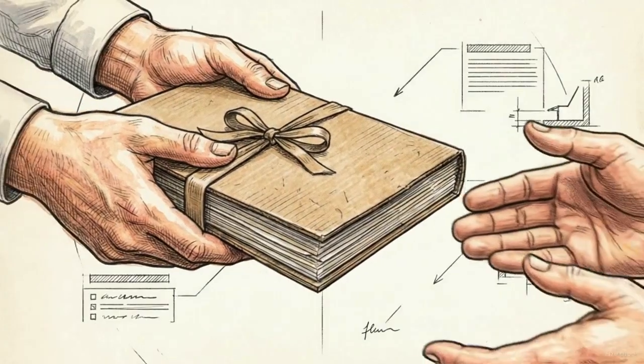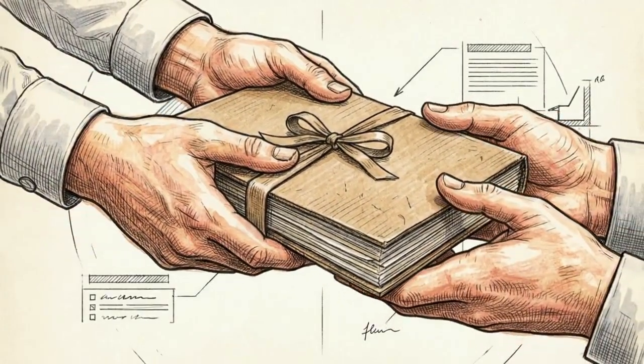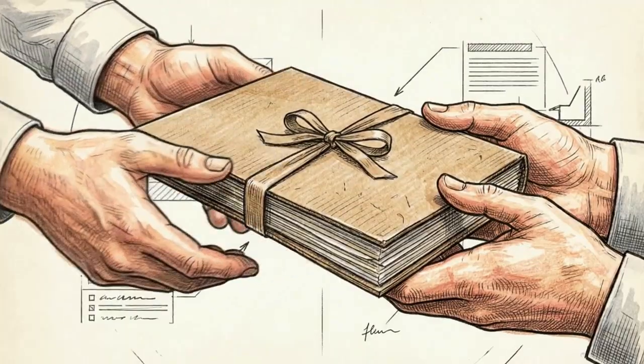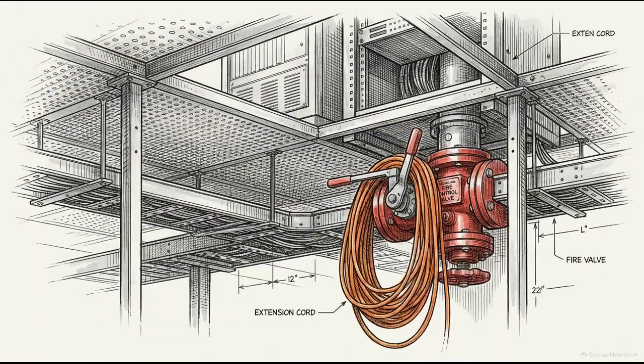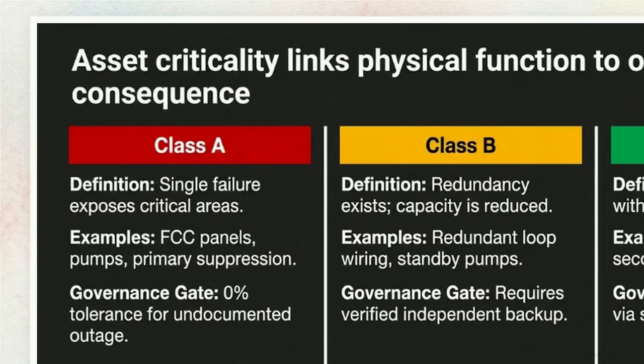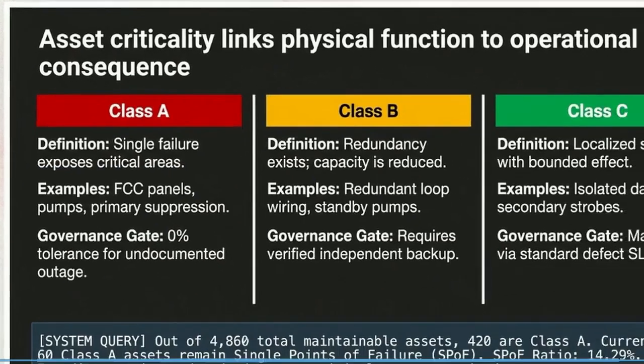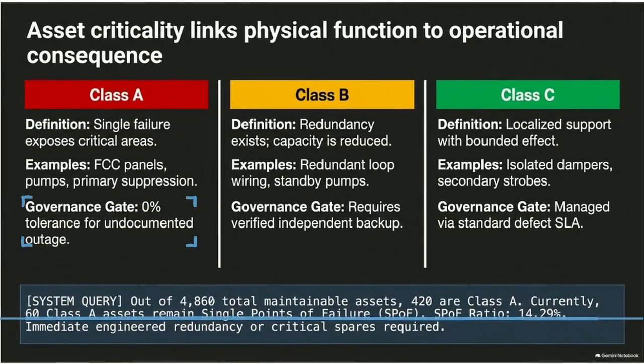The exact moment a fire system is formally accepted at handover is when its highest risk profile begins, as it is now subjected to the complexities of daily operations and human error. Operators classify equipment by asset criticality, where Class A means a single failure exposes a critical data hall. This system carries a single point of failure. Lacking redundant backups, it has a 0% tolerance for any undocumented outage.